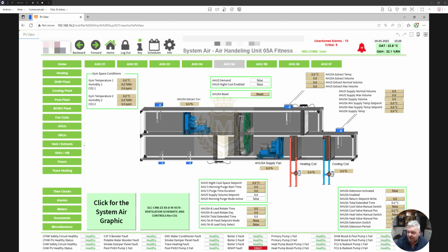That's got a heating coil and a cooling coil. Now, I don't know if this heating coil and cooling coil is the right way round. Normally I would see a cooling coil first and then a heating coil, but it must be on this graphic, because if we would have worked to the system air graphics, we've got the ventilation schematic there. In fact, let me just put you on pause a minute.